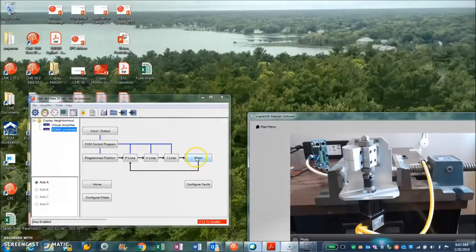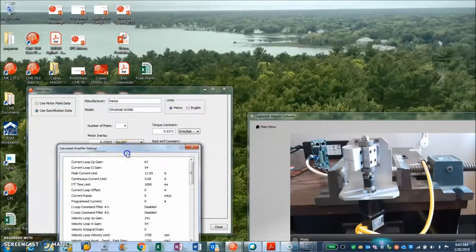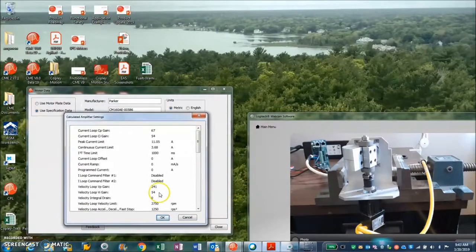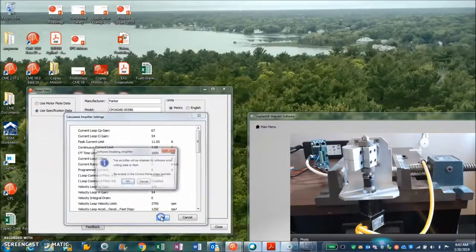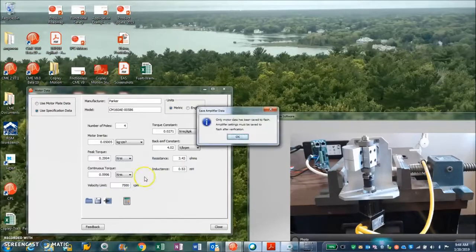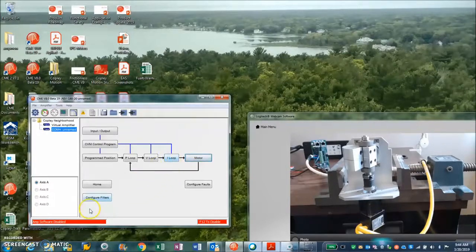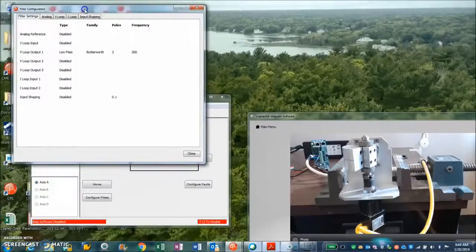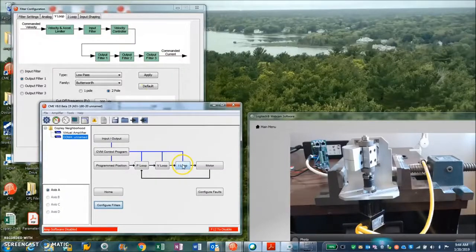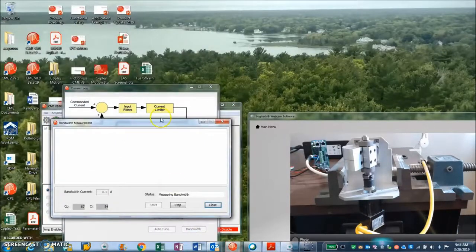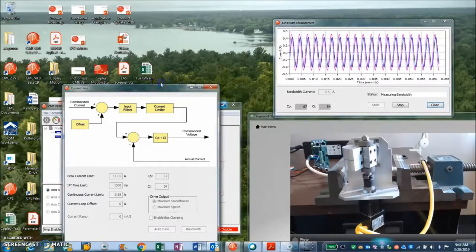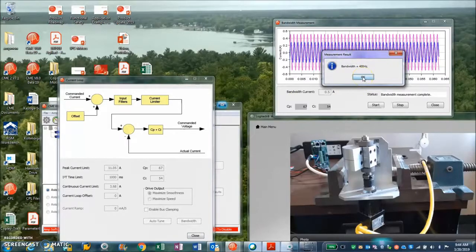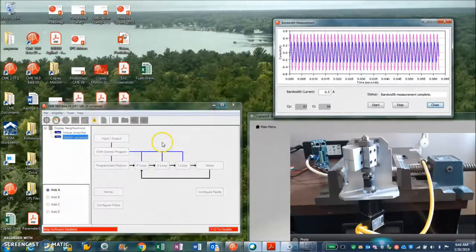We're going to look at some data for this motor. Originally we put in the inertia of the motor: 0.05 kilogram-centimeter squared. That used to say inertia because you could put the load in there too, and it calculates initial values. But the gains come up a little high when you have a large inertia, and there's a coupling, so we have to watch the filter frequency. There's a velocity filter frequency that we will adjust for the large inertia mismatch. I have a current loop based on the math model—I just need to make sure I have sufficient bandwidth. I like a kilohertz, but 400 hertz is good for today. We can tune the current loop later.